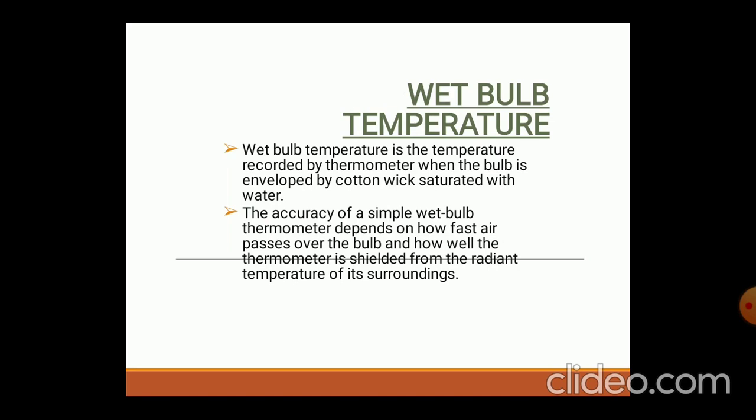What do we mean by wet bulb temperature? Wet bulb temperature is the temperature recorded by a thermometer when the bulb is enveloped by a cotton wick saturated with water. To take the wet bulb temperature, we have to cover the thermometer with a wetted cloth — it should be totally saturated with water. The accuracy of wet bulb temperature depends upon how fast air passes over the bulb and how well the thermometer is shielded from the radiant temperature of the surroundings.